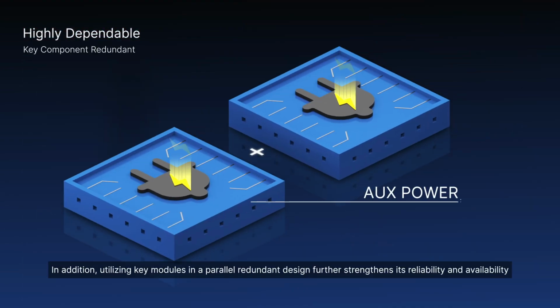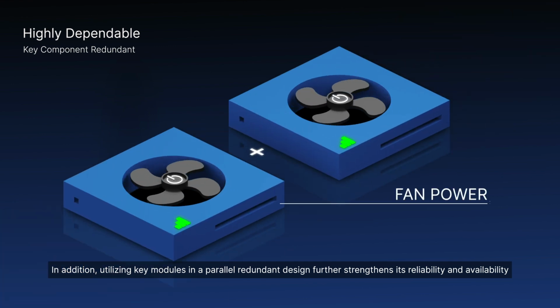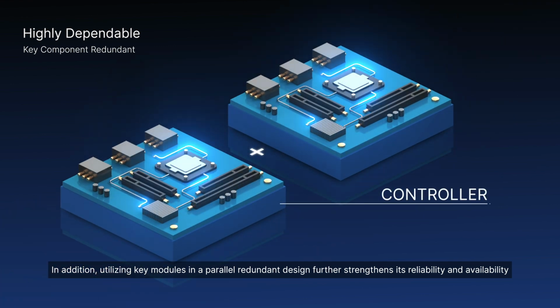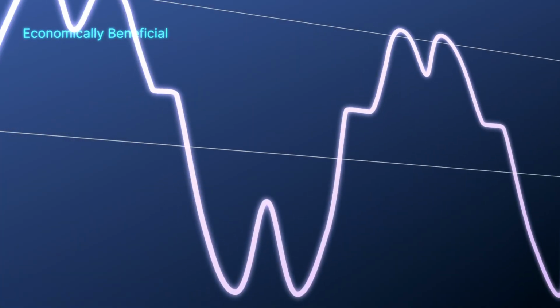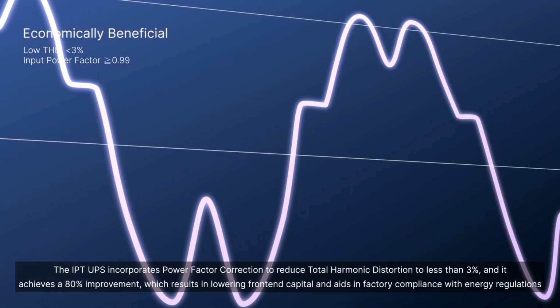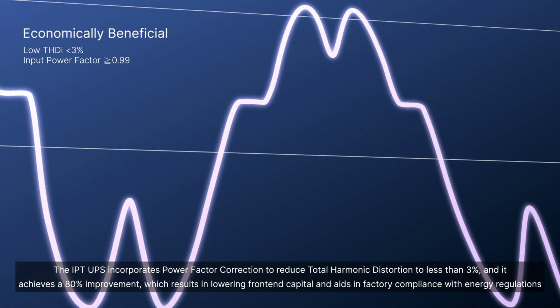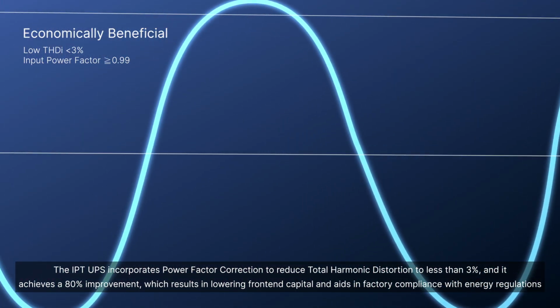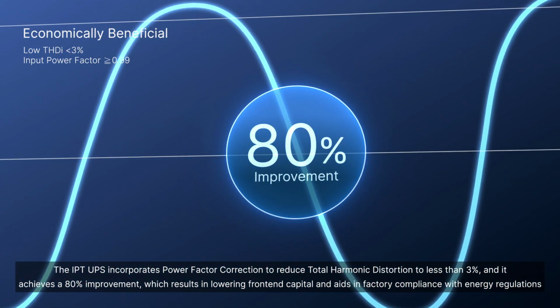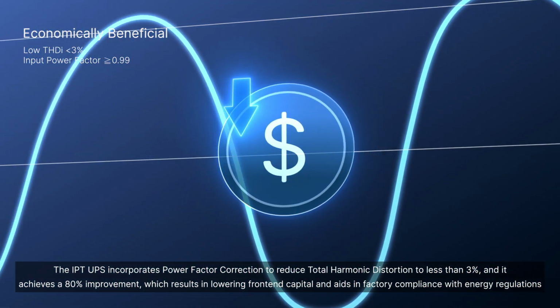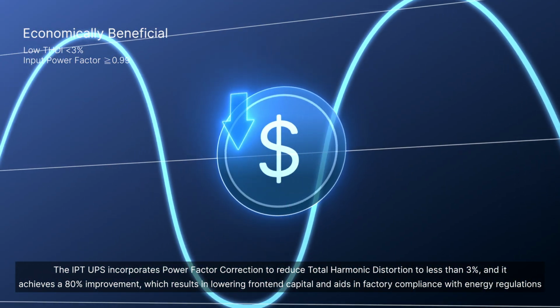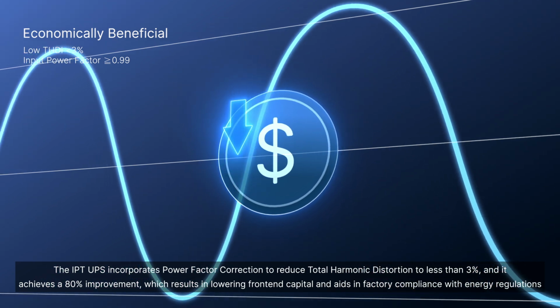Utilizing key modules in a parallel redundant design further strengthens its reliability and availability. The IPT UPS incorporates power factor correction to reduce total harmonic distortion to less than 3%, achieving an 80% improvement, which lowers front-end capital costs and aids in factory compliance with energy regulations.